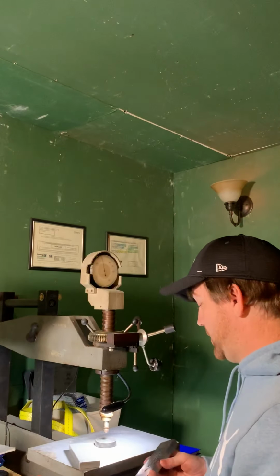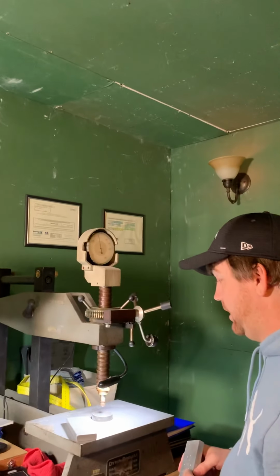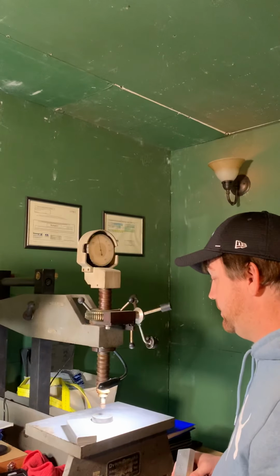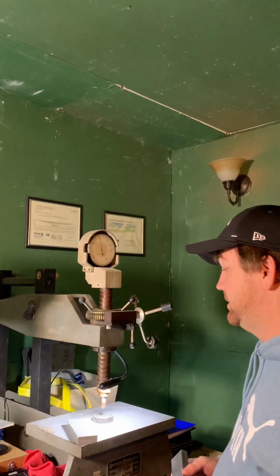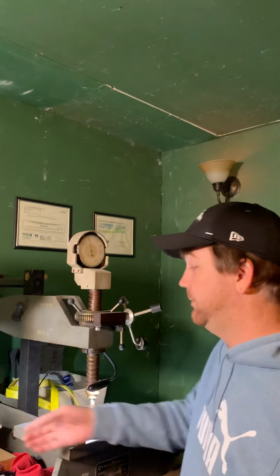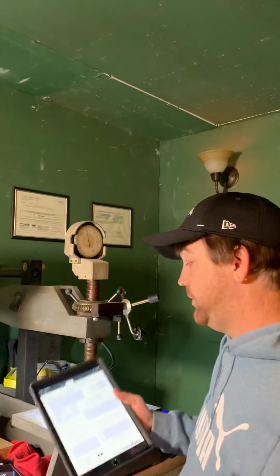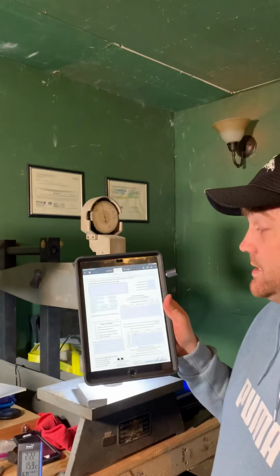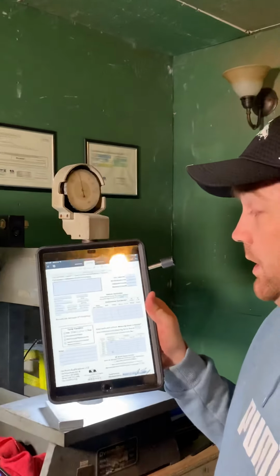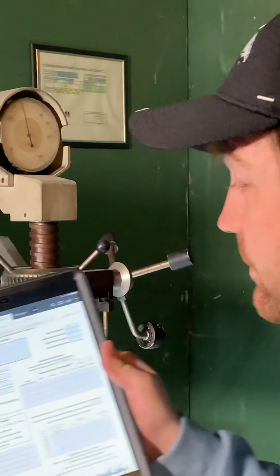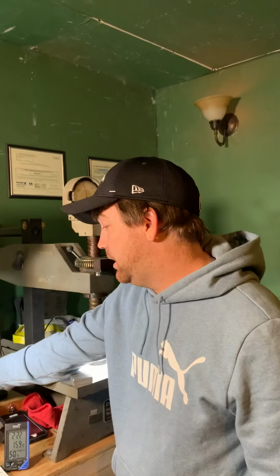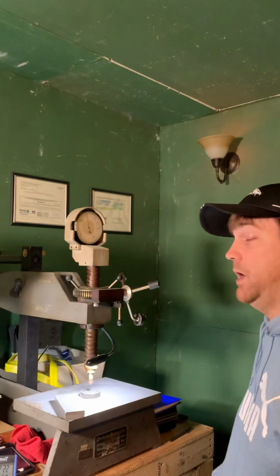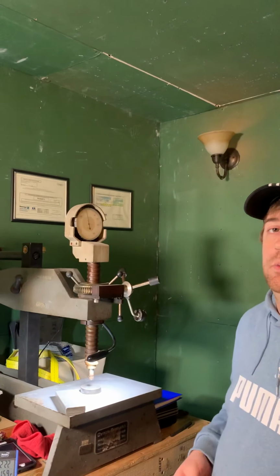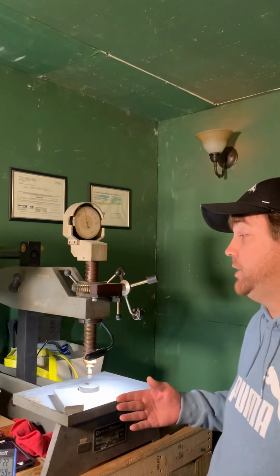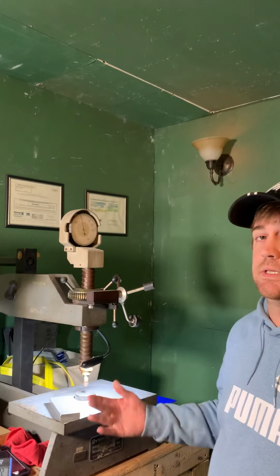You take 2 measurements per block, and if they're within tolerance, you do the same thing as the Rockwell. You record all of your measurements for as found and as left on your form. It does the math for you, and if it reads within tolerance, you send it to the quality manager, and the quality manager then releases it to the customer.